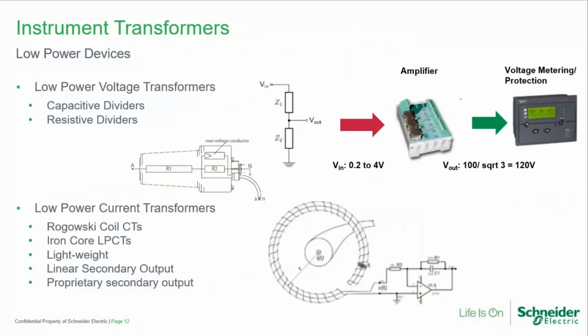So let's talk a little bit about some other considerations with these newer designs of medium voltage switchgear, and some of these considerations actually are starting to apply to traditional styles of medium voltage switchgear, including metal clad switchgear. So let's talk about some different instrument transformer types, low power devices, things like low power voltage transformers, low power current transformers. In the voltage transformer world, there's a couple of benefits from going to these low power devices.